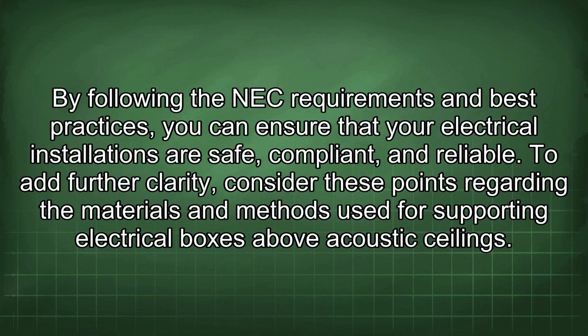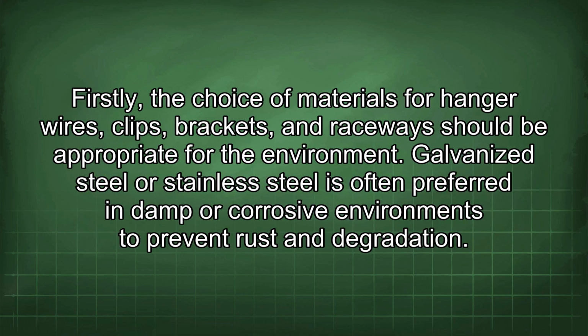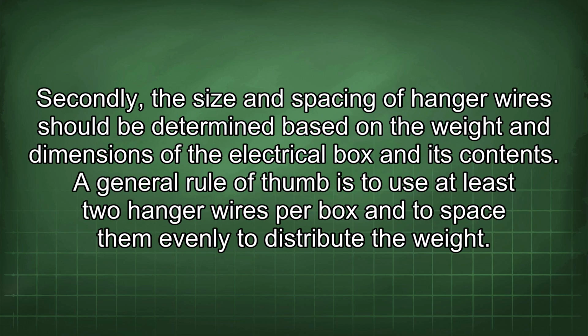To add further clarity, consider these points regarding the materials and methods used for supporting electrical boxes above acoustic ceilings. Firstly, the choice of materials for hanger wires, clips, brackets, and raceways should be appropriate for the environment. Galvanized steel or stainless steel is often preferred in damp or corrosive environments to prevent rust and degradation. Secondly, the size and spacing of hanger wires should be determined based on the weight and dimensions of the electrical box and its contents. A general rule of thumb is to use at least 2 hanger wires per box and to space them evenly to distribute the weight.